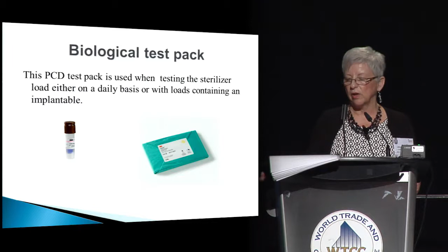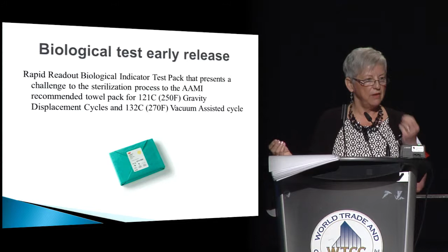Biological test pack early release. This is one that has a test pack and it has an emulating integrator in it. And based on the indicator, you can release your load, but you still need to follow up with that biological, because many loads are released within the hospitals prior to the biological read. This gives you a little bit more assurance that, in fact, you've got a successful load there. And so it's really a good thing for the hospitals that have to release devices before the BI.